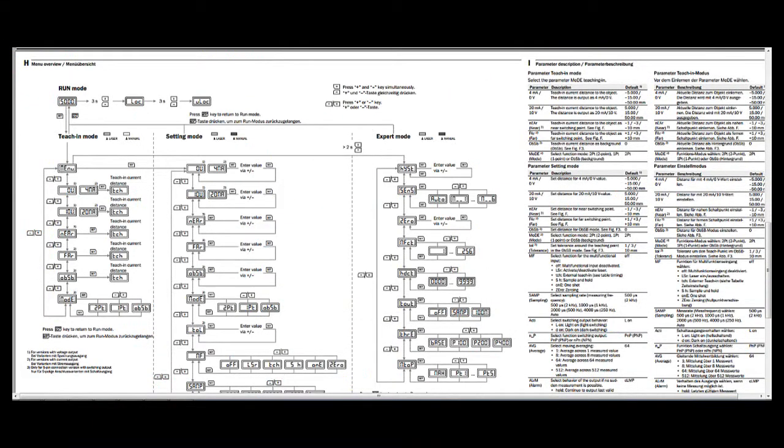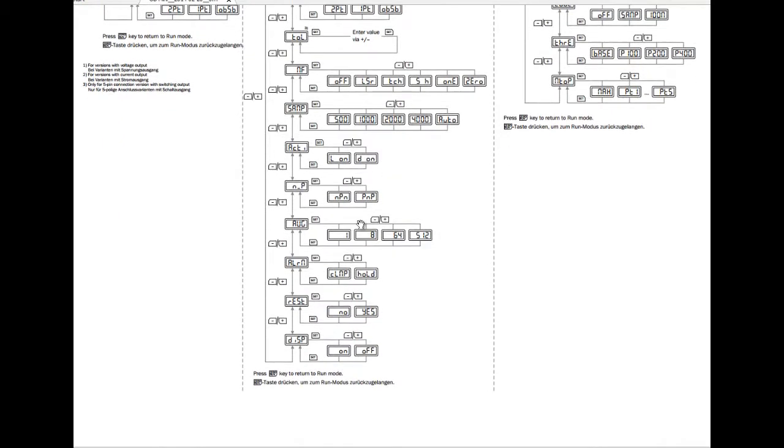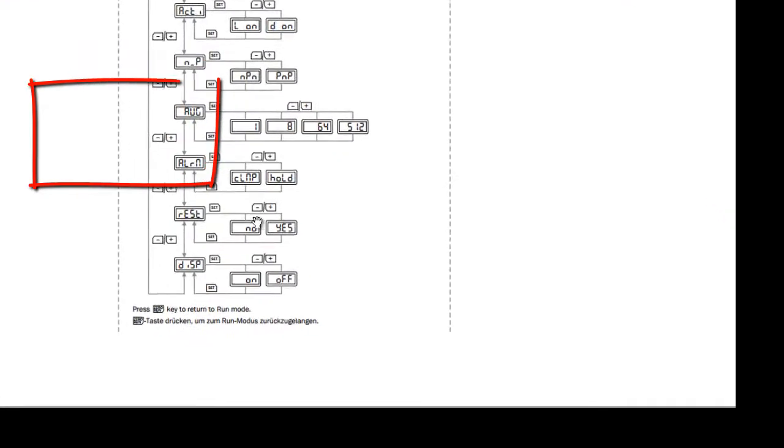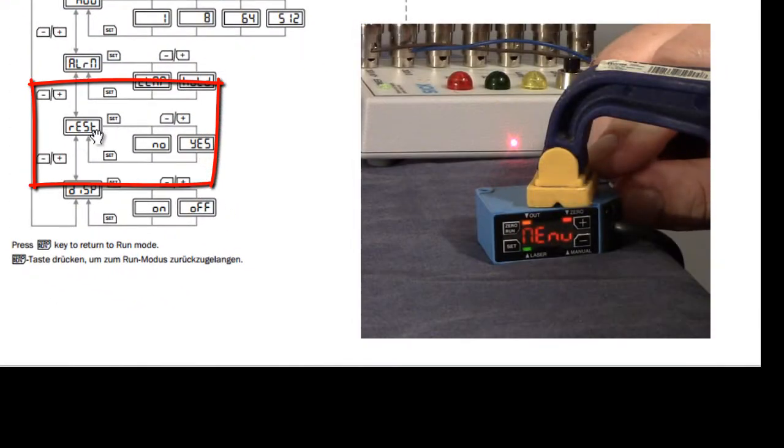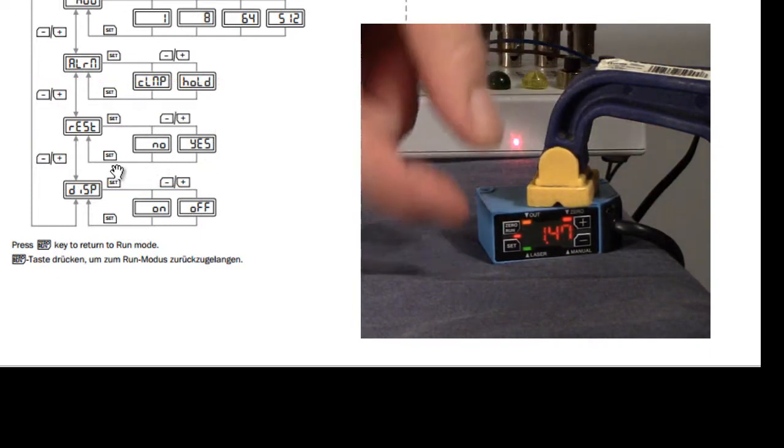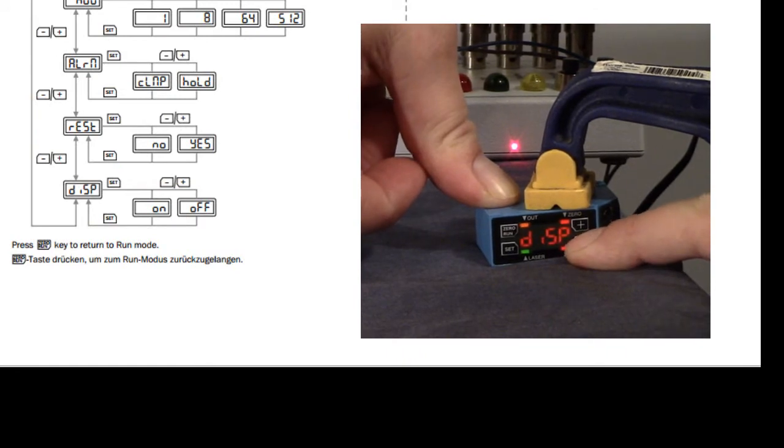One of the first things we should do is reset the sensor back to factory defaults. So we know where we're starting from and so we can move forward in a normal manner. To do that, you can see on the second page of the insert under the run mode. This is more of an advanced setting. And then at the bottom, we have reset, R-E-S-T. So we're actually going to do that first. Go into R-E-S-T, hit set, change it to yes, hit set again. And then we can hold the run button to get back to normal run mode.